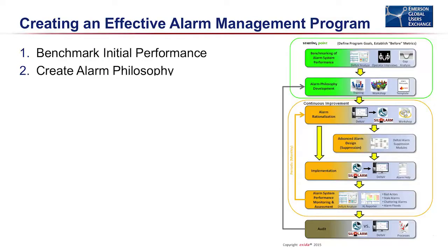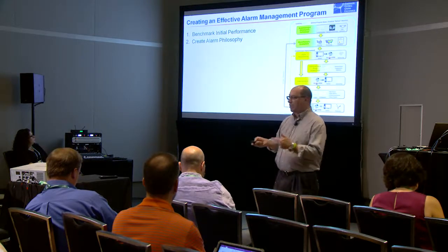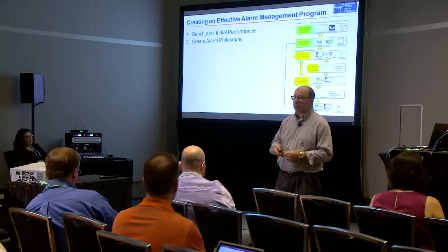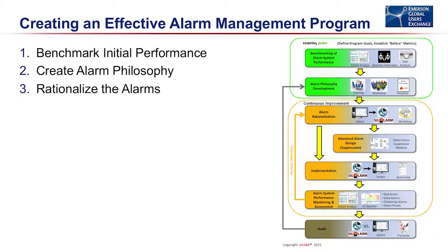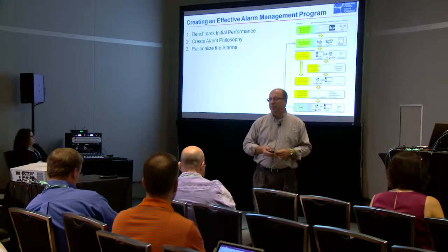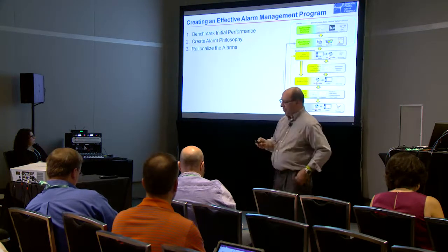Second step, in this case, is to create an alarm philosophy document. What's the guideline or standard for doing alarm management at your particular site? How do you prioritize alarms? Things like that. Third step is to rationalize the alarms. Go through that process of evaluating the alarms, making sure they meet the definition and other criteria.